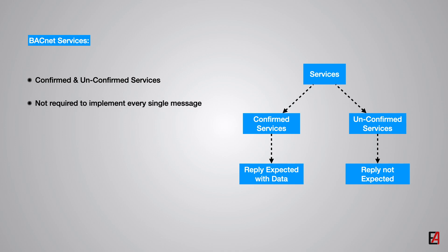BACnet devices are not required to implement every single service. Just one service, read property is required to be processed by all the BACnet devices. Depending upon the function and the complexity of the device, additional services may be initiated.